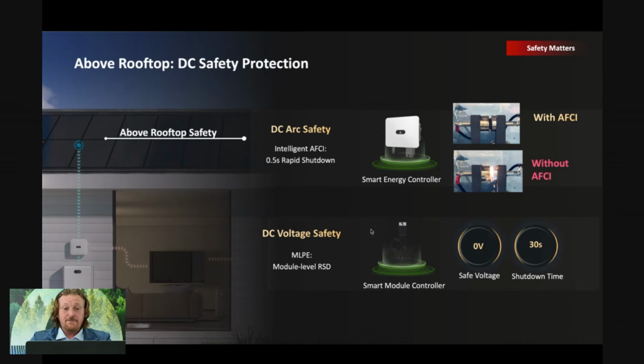Now, with this safety feature, with the PV optimizers, we can achieve 0 voltage on the panels in less than 30 seconds - from full voltage to 0 voltage in less than 30 seconds. This is called rapid shutdown, and it provides a level of safety for the installers, for maintenance teams, and for firefighters.